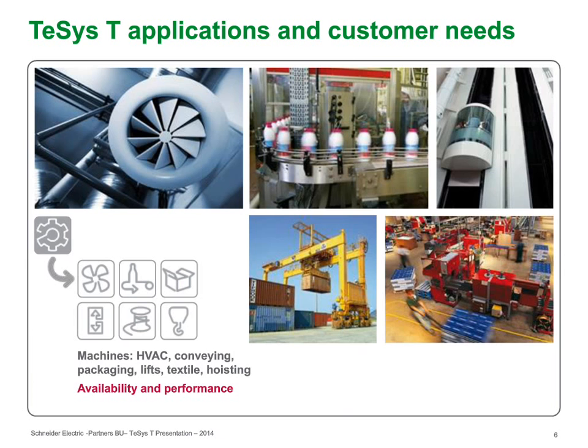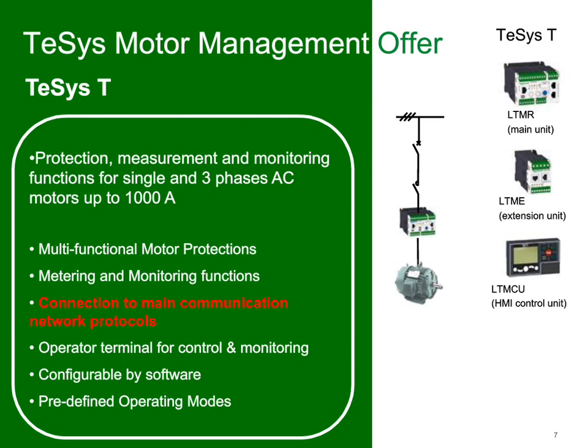So before I tell you some of the details here, let's see if we can tell you what TeSys T is. In the upper right-hand corner you see that LTMR. That looks like, and it actually is, a solid-state overload relay that you would put with a motor. There are current transformers. There are 3 holes in the back of that unit for 3-phase power. The picture on the left side shows only one of the conductors coming through it. What we can do with a current transformer is detect the amount of current running through a wire, and so with this particular unit, we can measure current.